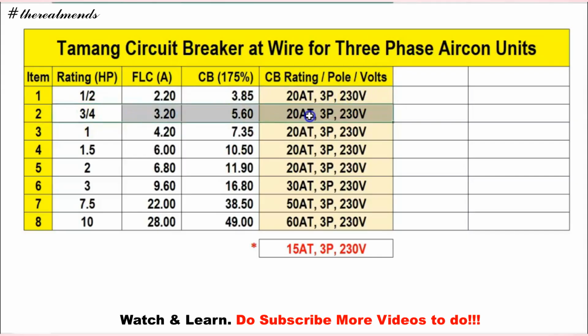Sa 3/4, that is 5.6, so 20 ampere trip 3 phase 230 volts. Sa 1 HP, 20 ampere trip 3 phase 230 volts. Sa 1.5, the same ng meron tayong CB capacity na 10.50, so 20 ampere trip 3 phase.